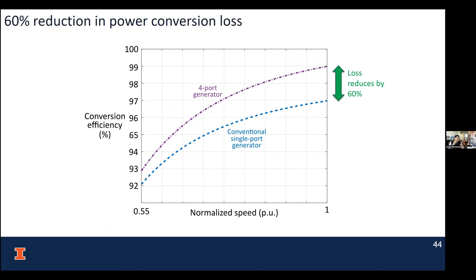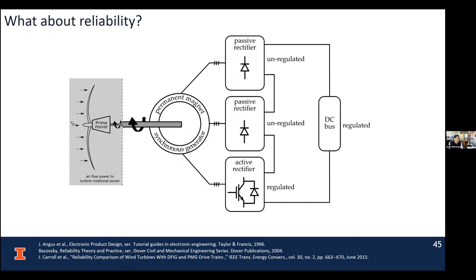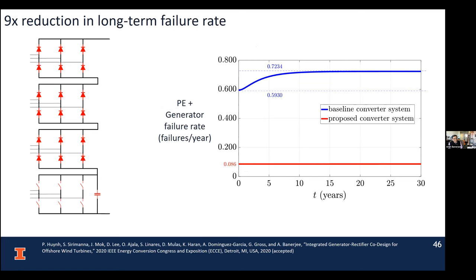The last piece of the puzzle: we talked about power density in terms of VA rating and eliminating capacitors, and we talked about efficiency. What about reliability? Think about it -- the majority of these power devices are basically diodes, and diodes are inherently much more reliable than IGBTs based on the data we have. In this four-port design, where the majority of the power is processed by diodes and we've eliminated the capacitors at the passive ports, the reliability improves drastically.